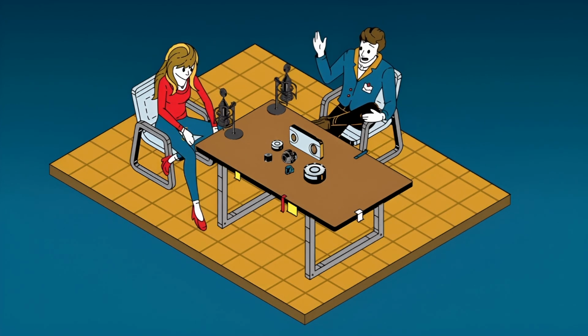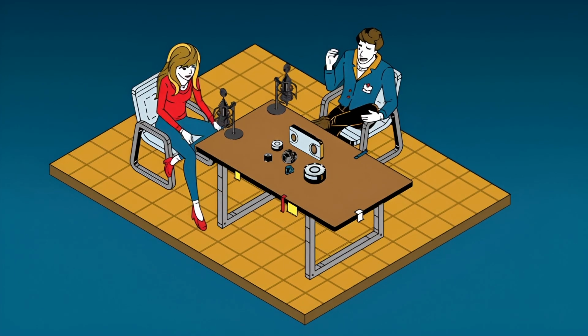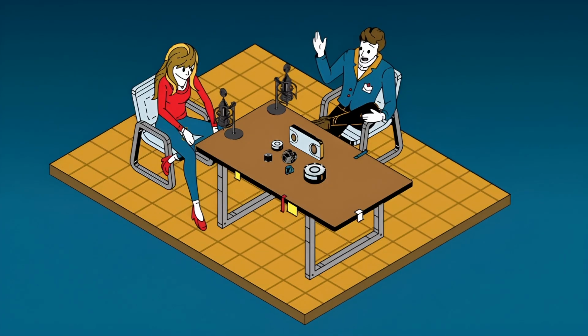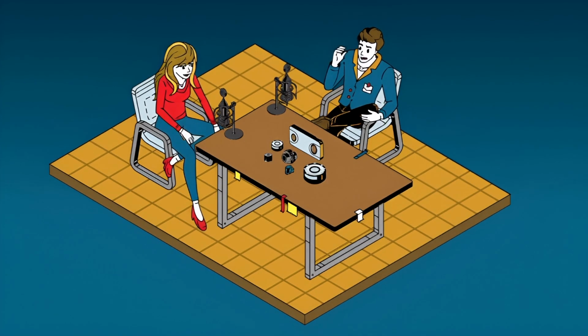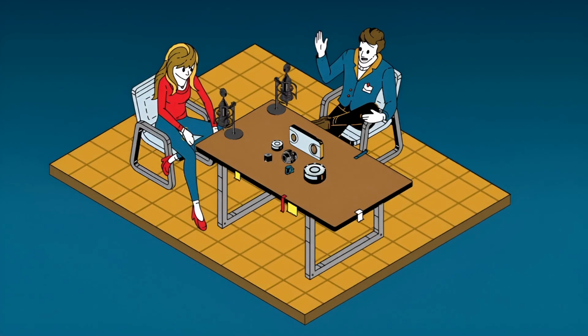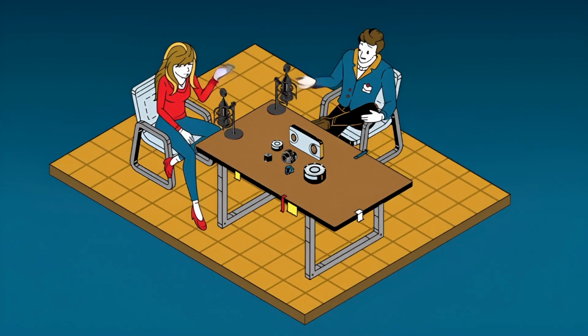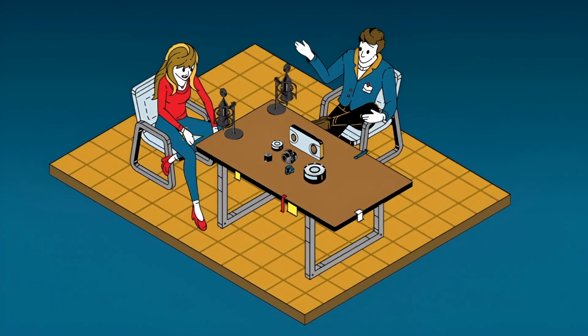Exactly. Miniature load cells use incredibly complex internal geometries, what we call the load path. The load path. Yeah. The outer structure of the sensor absorbs and routes that massive crushing force entirely away from the delicate measurement zones. Wow. So the strain gauge only sees a highly controlled, predictable, microscopic fraction of that total load. So they're engineering the stress path to basically bypass the delicate electronics entirely?